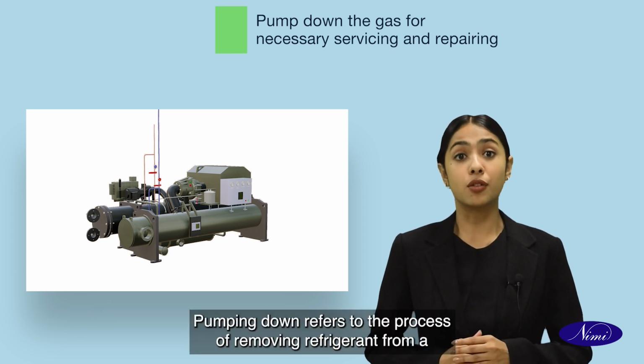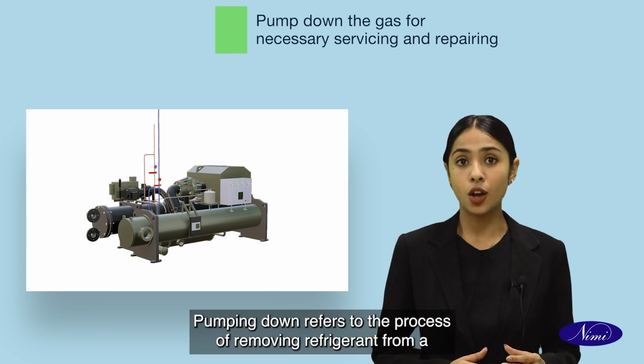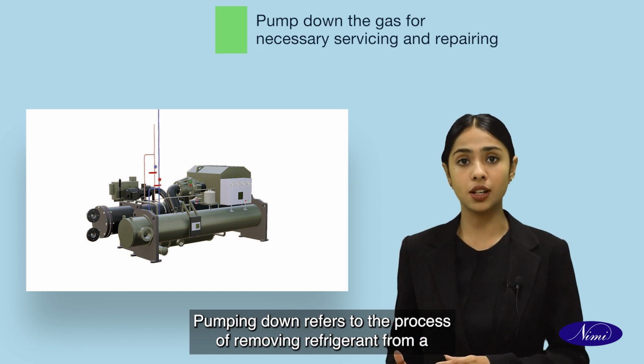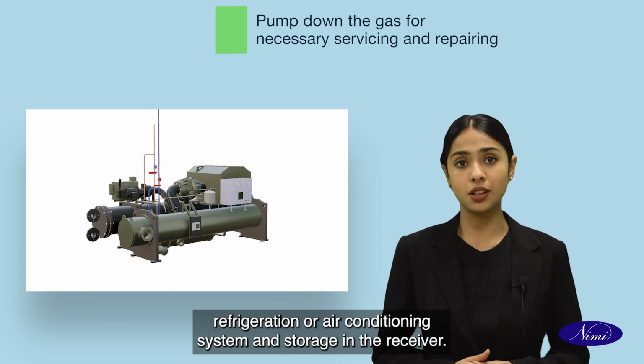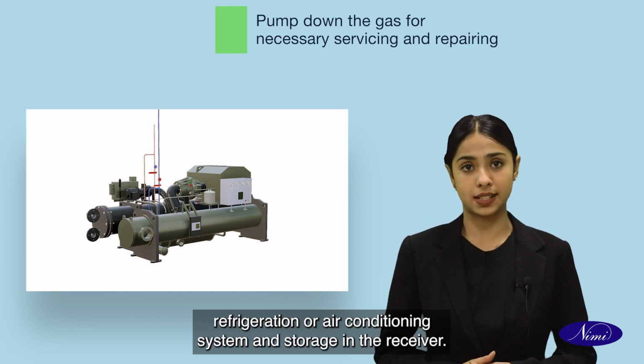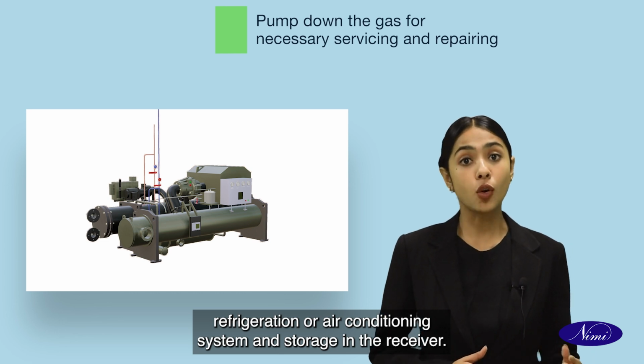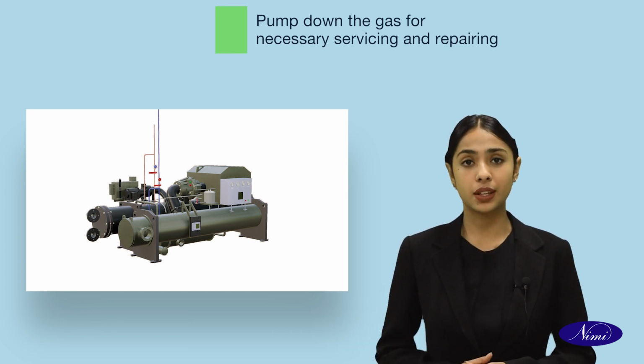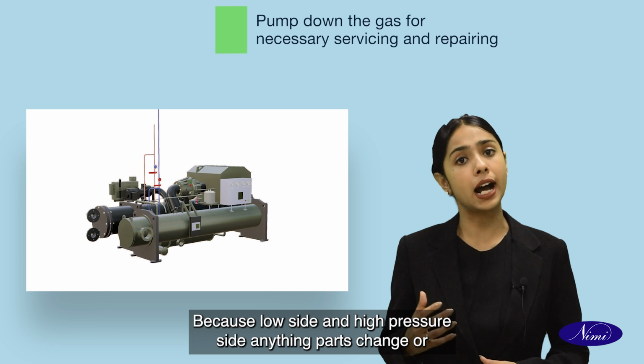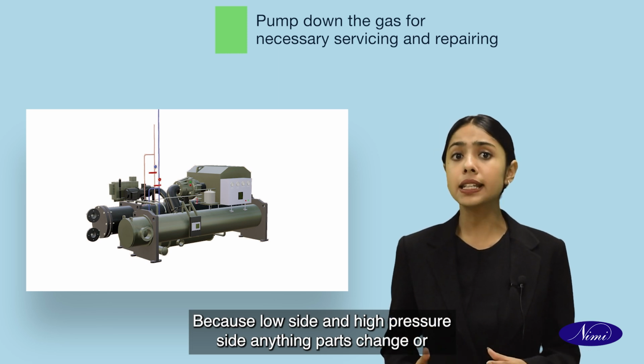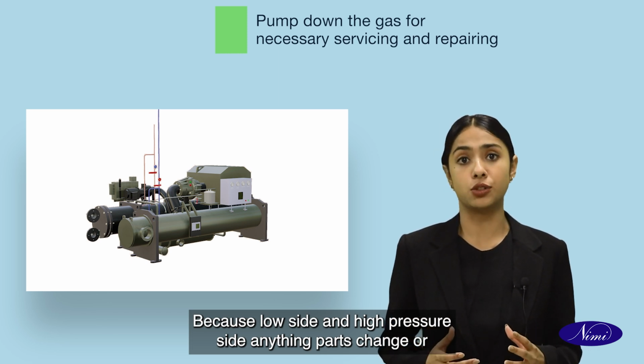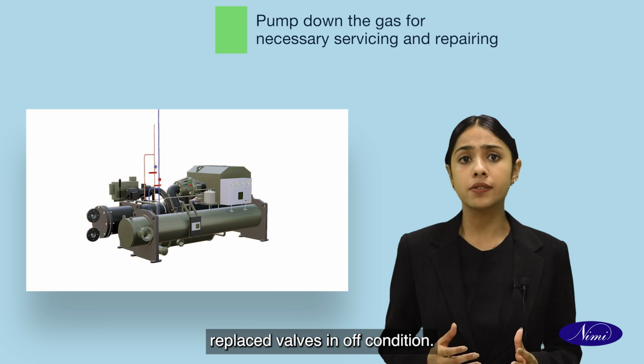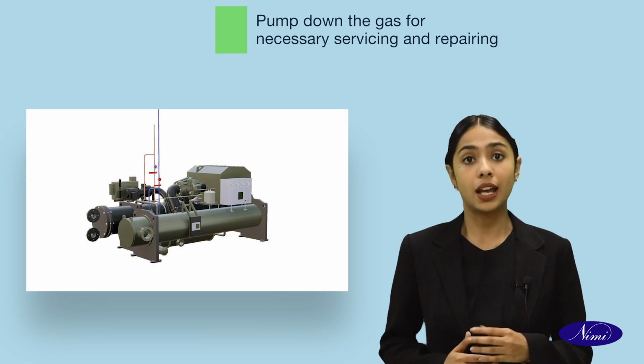In this session, we are going to learn about pumping down the gas for necessary servicing and repairing. Pumping down refers to the process of removing refrigerant from a refrigeration or air conditioning system and storing it in the receiver, because parts on the low side and high pressure side can then be changed or replaced with the valves in off condition.